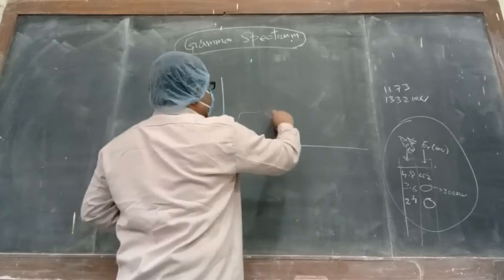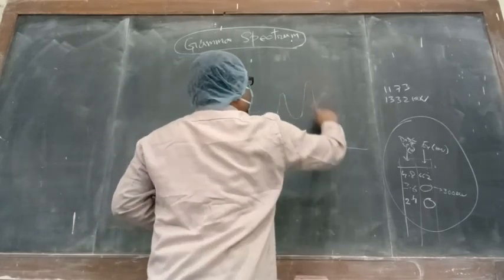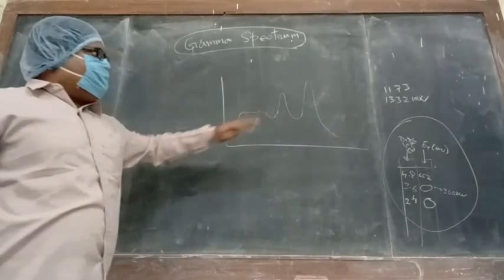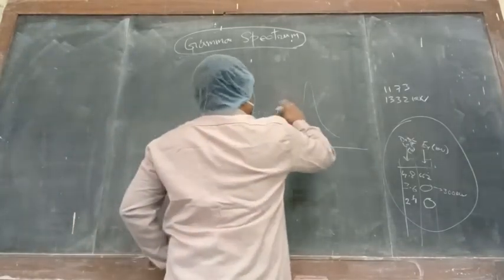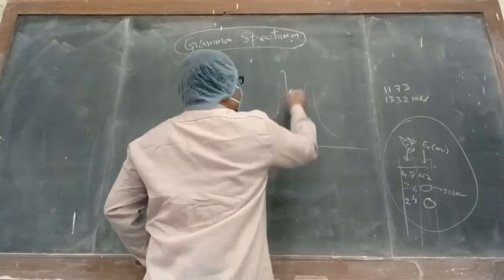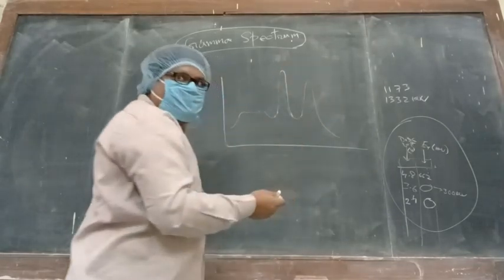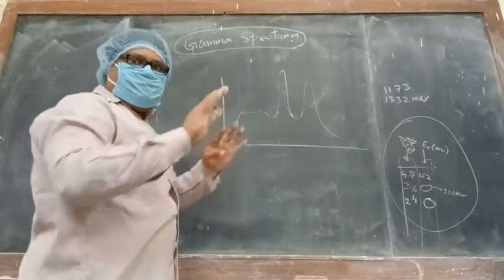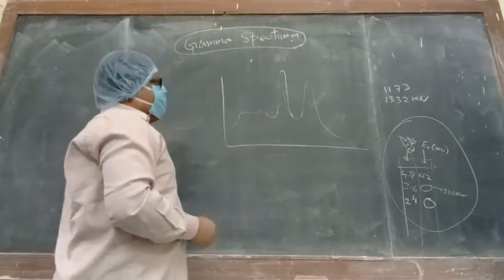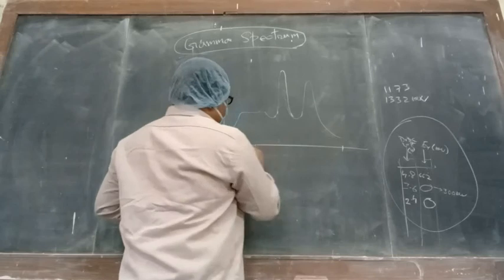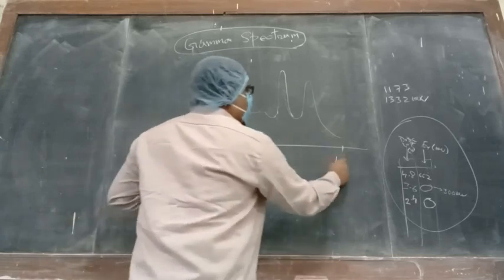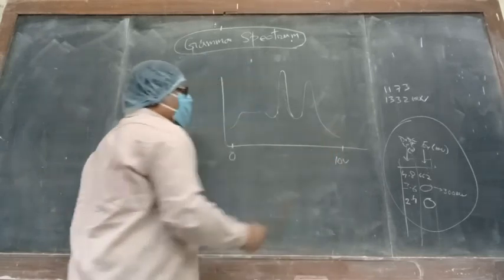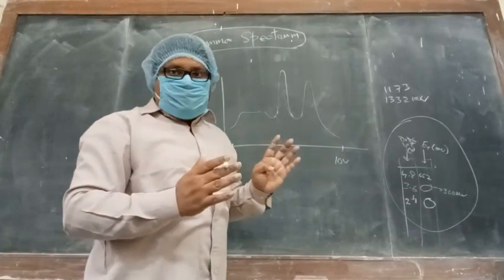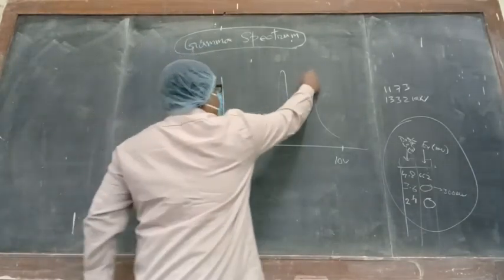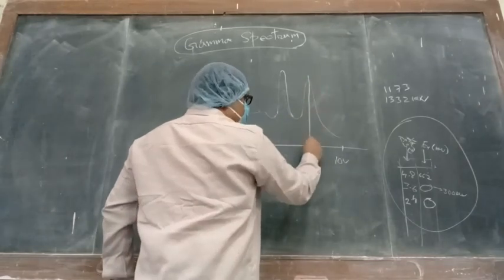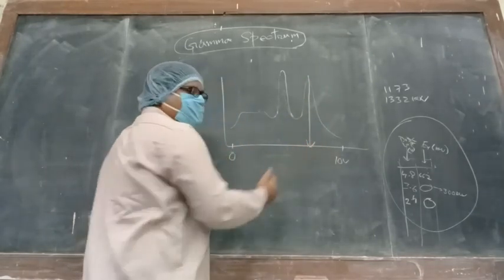From the cobalt-60, we expect a spectrum like this, or maybe like this. Which one will be high also depends on the efficiency of the detector. That part I will speak to you about later on. Now, the first thing to note is that in our detector, we have an inherent limitation in this setup that all data must be between 0 and 10 volts, right? So this peak of 1332 must arrive at some point below 10 volts.